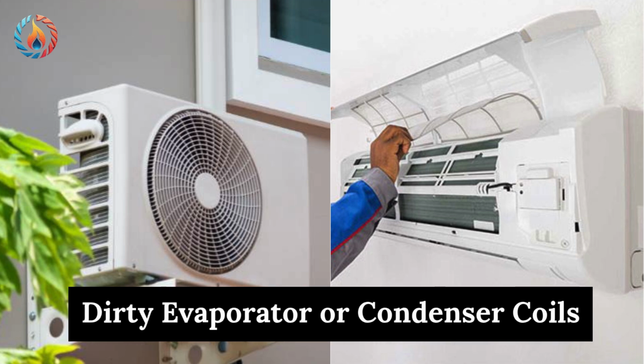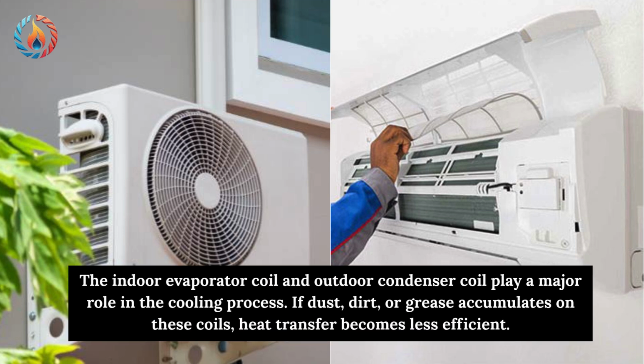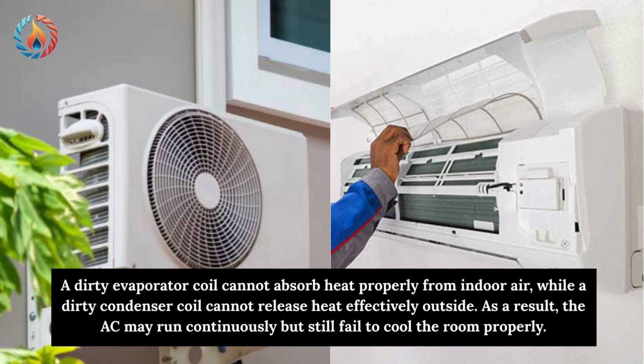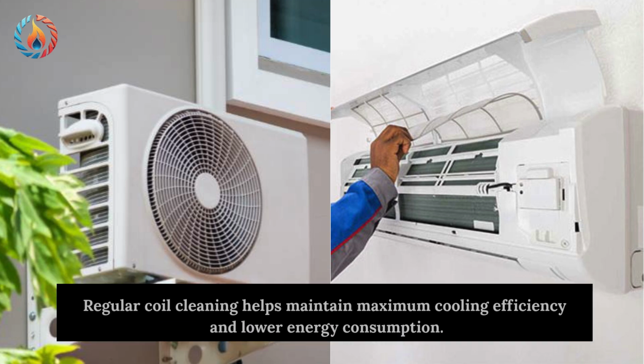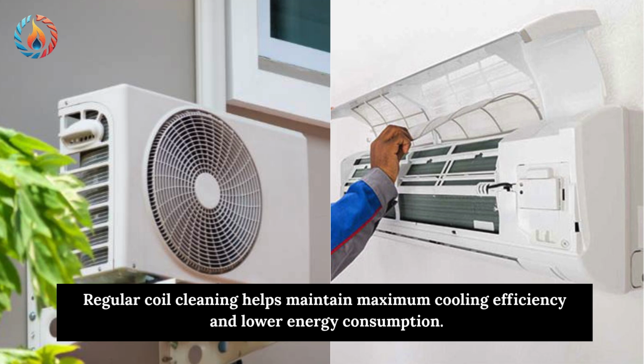Dirty evaporator or condenser coils. The indoor evaporator coil and outdoor condenser coil play a major role in the cooling process. If dust, dirt, or grease accumulates on these coils, heat transfer becomes less efficient. A dirty evaporator coil cannot absorb heat properly from indoor air, while a dirty condenser coil cannot release heat effectively outside. As a result, the AC may run continuously but still fail to cool the room properly. Regular coil cleaning helps maintain maximum cooling efficiency and lower energy consumption.